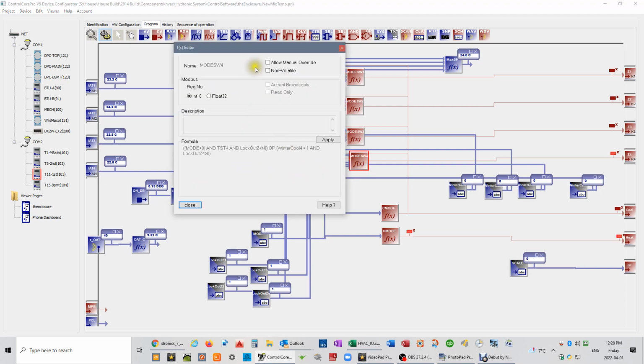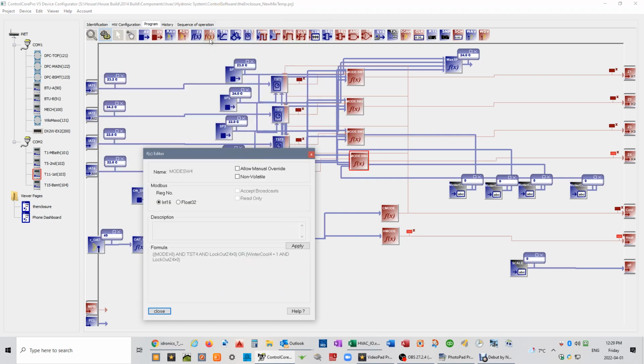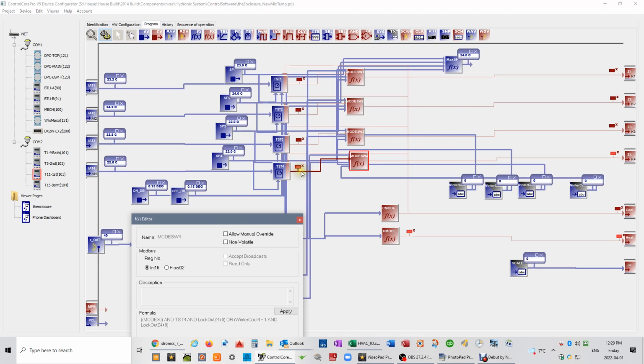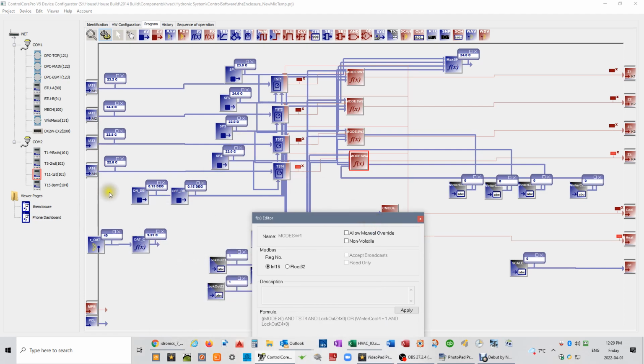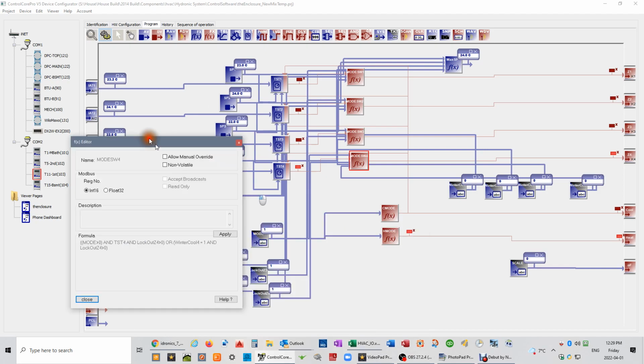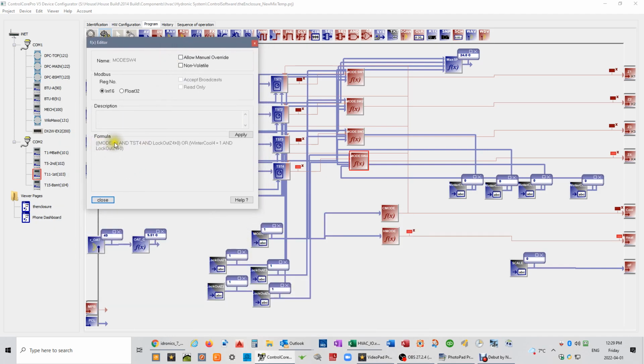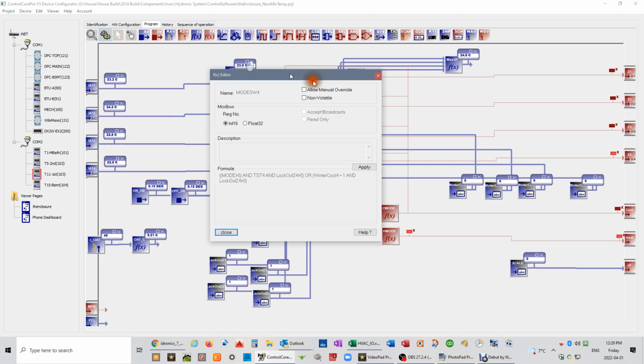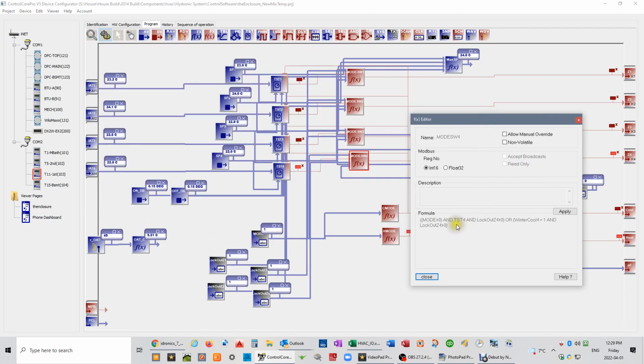But if we go now to this last bit, this is a digital function block, and it's digital because it's basically acting on 0 and 1, on off kind of thing, as opposed to an analog which has multiple values that it's acting on. And it's saying mode is greater than 0, and mode in our case is indicating, are we in heating mode or cooling mode? Heating mode's 1, cooling mode's 2, efficiency mode is 3, and off is 0. So it's saying if we're greater than off, and T-stat 4 is true, and in this case it's true, and lockout is greater than 0.